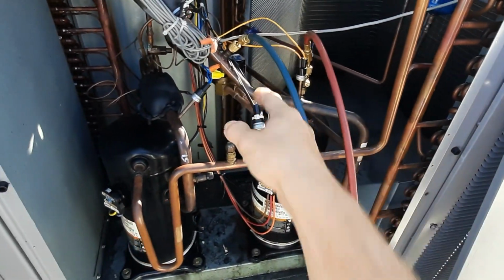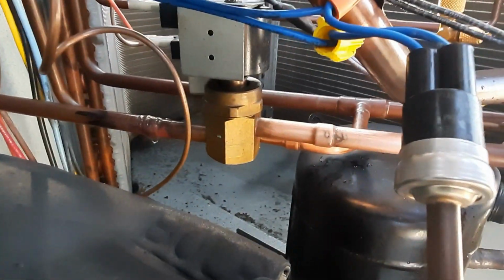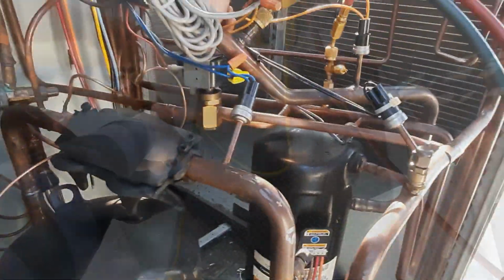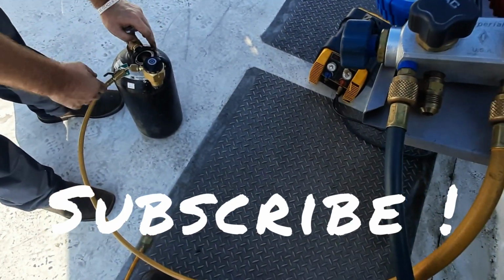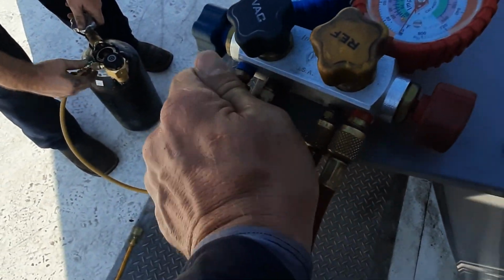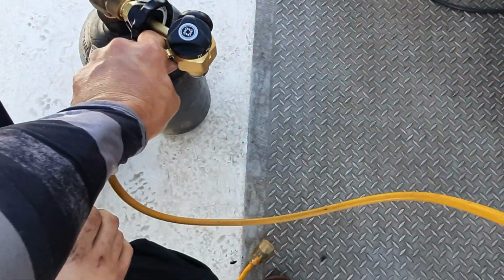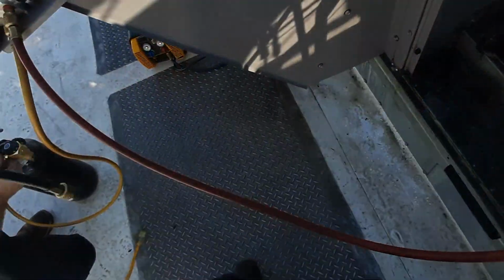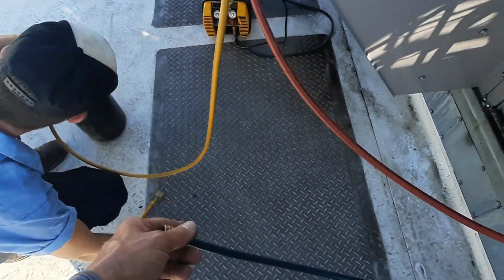Now you got them cleaned up, go ahead and pop that solenoid off of there. Take a screw out of the top, it should slide right off. Yeah, hook up to the nitrogen tank. Turn it on, set it to purge. There you go. We're just going to unhook. The gasket's probably, we'll get a new gasket in that, it'll be alright. We just unhook our suction line, that way we're purging through. And then set it to braze, and we'll get this thing unbrazed.